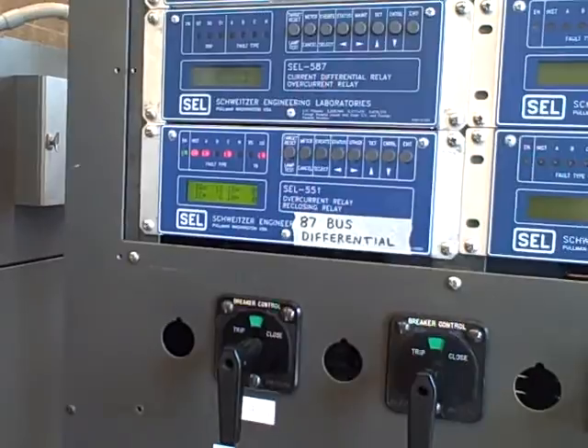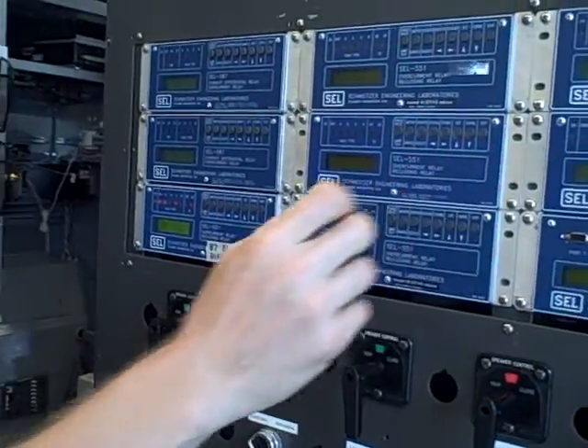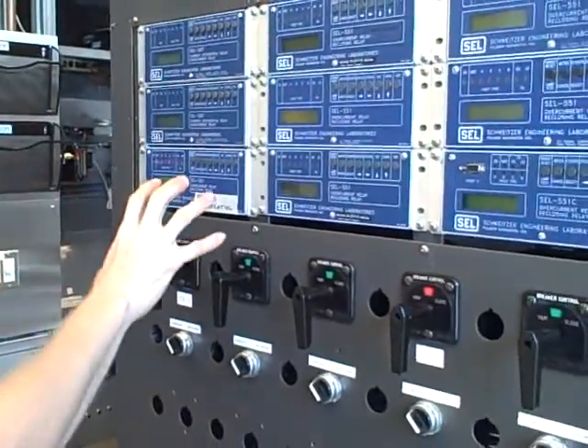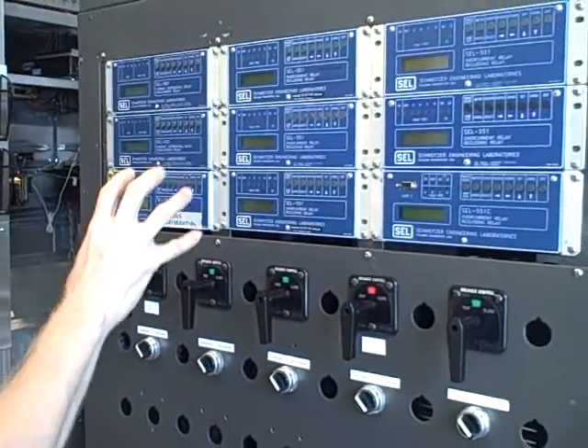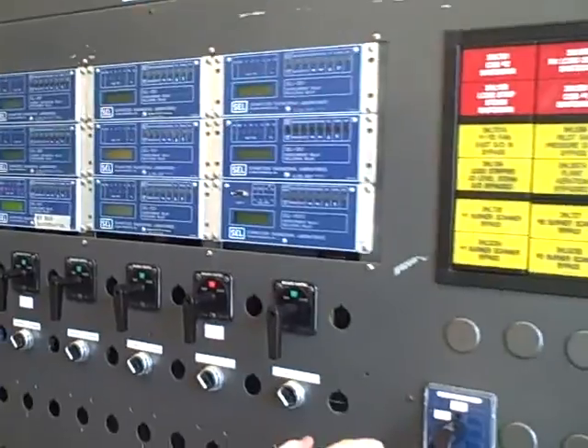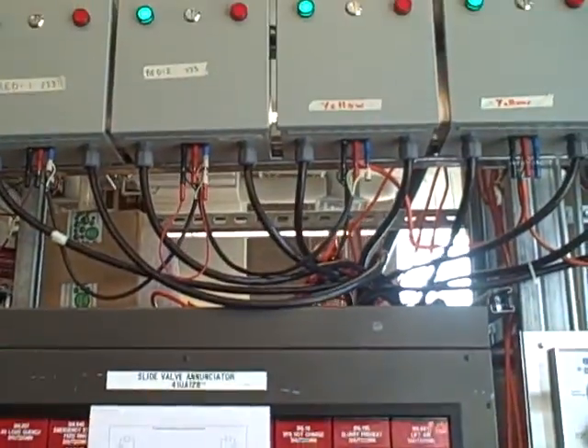So, a quick demonstration of a faulted bus on a single bus, five terminal substation, the use of 87 bus differential protection to detect the fault, how it trips the lockout relay, and how that lockout relay subsequently trips all five of the breakers on that single bus.